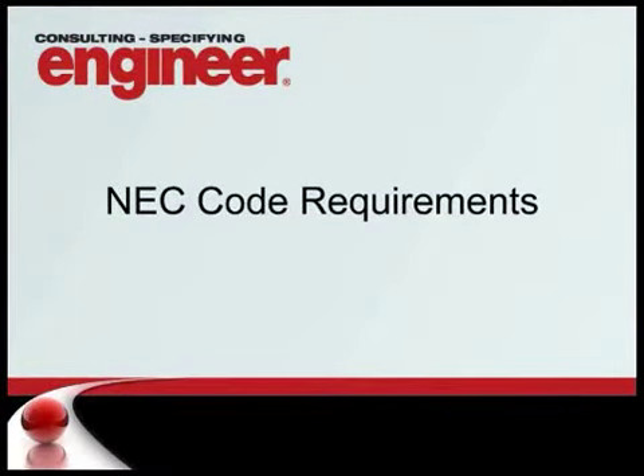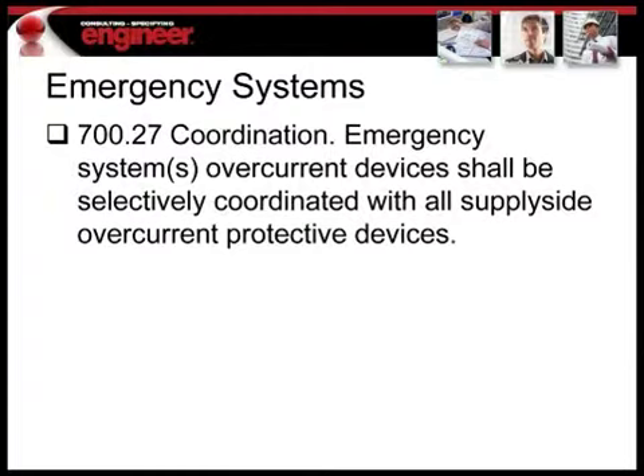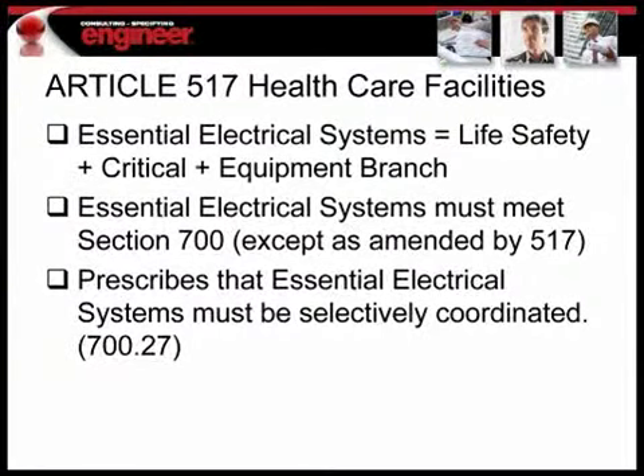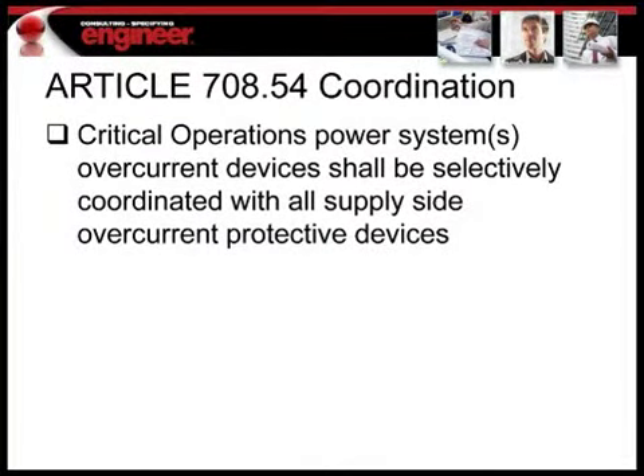And we'll cover some code sections. 700 again defines the fact that all emergency systems need to be selectively coordinated. And then Article 517 effectively links the essential power distribution system back to Article 700, where it prescribes that the emergency power distribution system must be selectively coordinated. So this basically goes over the definitions and the codes that prescribe that the essential branches in healthcare buildings have to be selectively coordinated. It also goes on to state that the critical operations branch of power needs to be selectively coordinated as well.